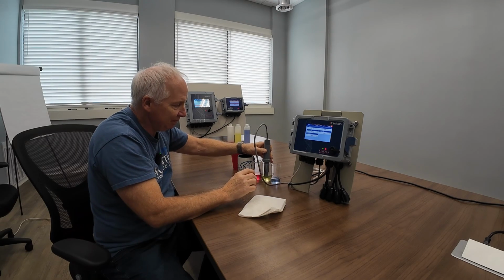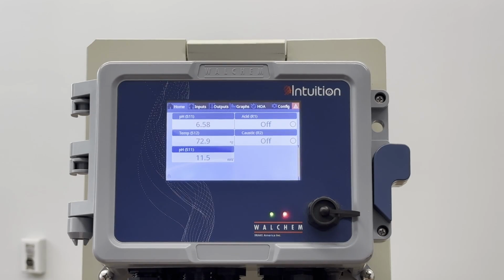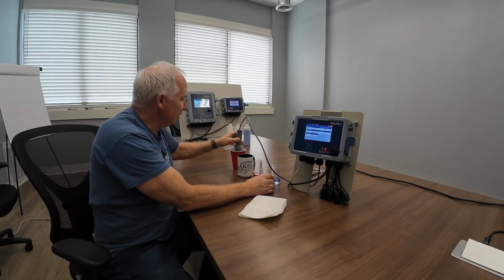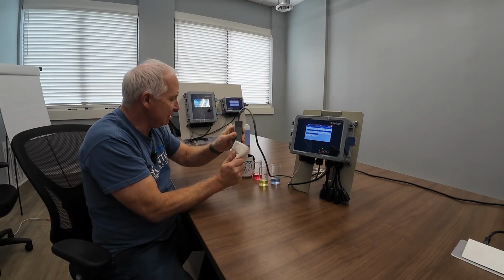So if I put it in 7, we'll see if it goes to 7. And my goal is if I'm within 1/10 of a pH unit, it's a pretty good calibration. So we're closing in on 7. 6.99, 6.98. I'm happy with that. So I will clean it for the last time here.